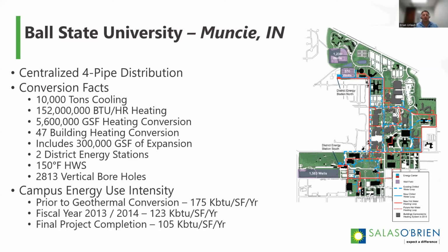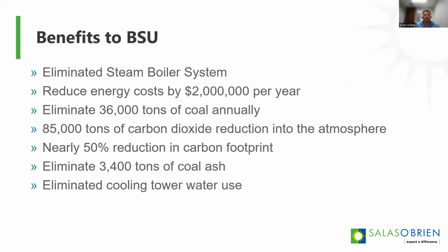So one of the big challenges is getting facility directors and managers on these campuses to start turning their systems down to figure out what is the lowest temperature you can operate at before you start to have comfort complaints. And that's one of the ways you can really figure out what your design temperature needs to be. And that's exactly what we did here to figure out the 140 was actually the lowest. We designed it for 150 to have a little safety factor, but they operate it right around between 140 and 150.